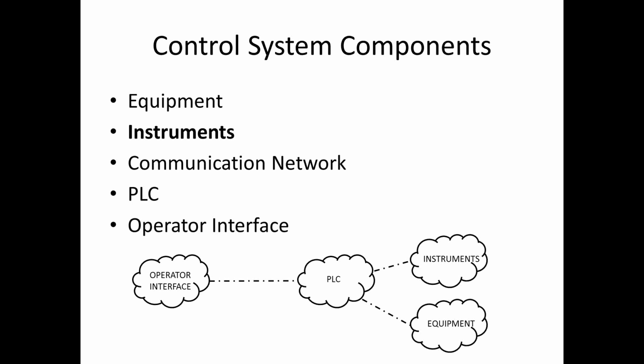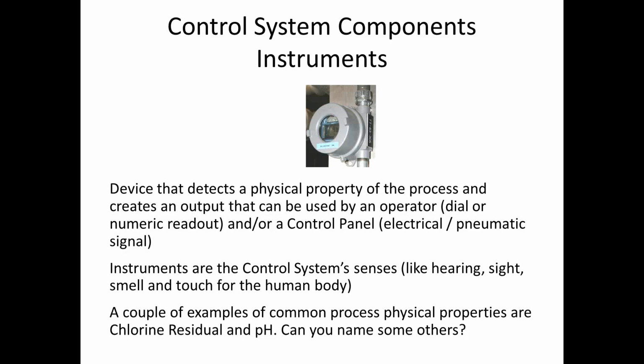We'll talk a little bit about the instrumentation within the control system. If you go out and look at the process, if you pour a sample of solids out on your desktop or your tabletop, you can tell the difference between a sample that is 1% solids and a sample that is 7% solids. You can tell whether you've got flow going down a flume, whether it's closer to 500,000 gallons a day or 5 million gallons a day. And you do that by your senses, your hearing, your sight, your smell, and touch. And that's basically what instrumentation is for.